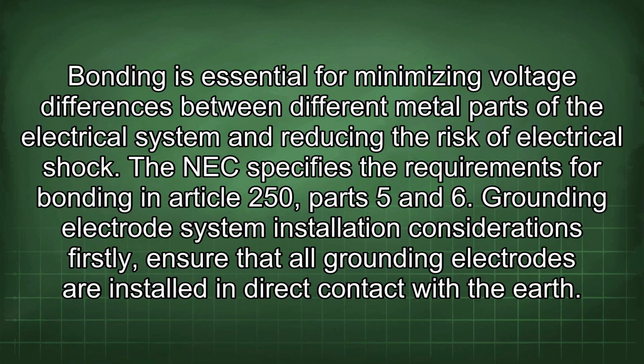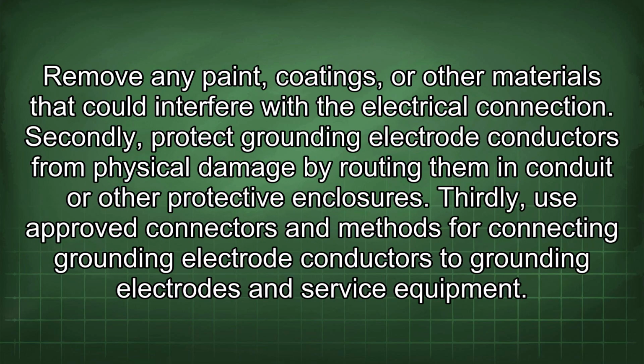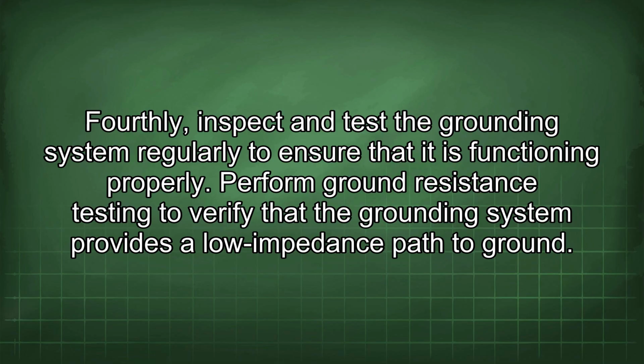Grounding electrode system installation considerations. Firstly, ensure that all grounding electrodes are installed in direct contact with the earth. Remove any paint, coatings, or other materials that could interfere with the electrical connection. Secondly, protect grounding electrode conductors from physical damage by routing them in conduit or other protective enclosures. Thirdly, use approved connectors and methods for connecting grounding electrode conductors to grounding electrodes and service equipment. Fourthly, inspect and test the grounding system regularly to ensure that it is functioning properly. Perform ground resistance testing to verify that the grounding system provides a low impedance path to ground.